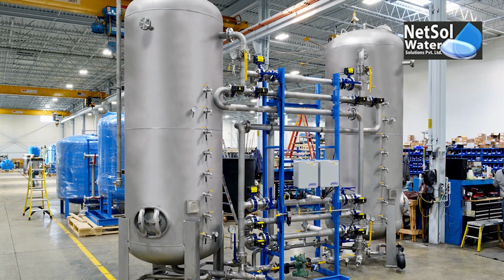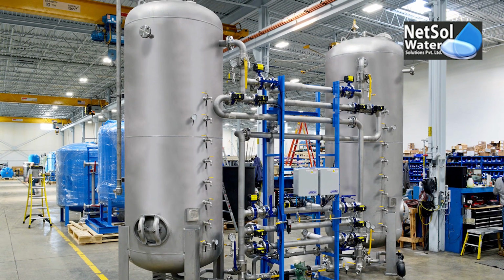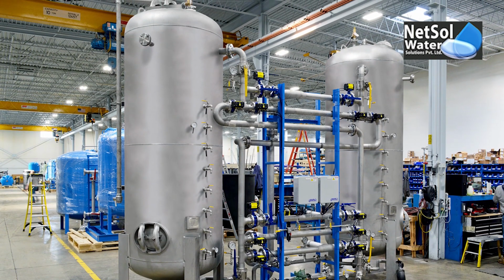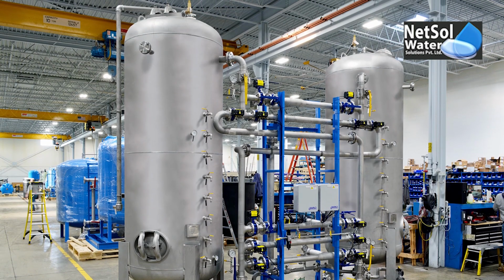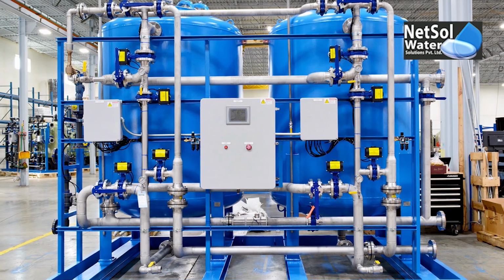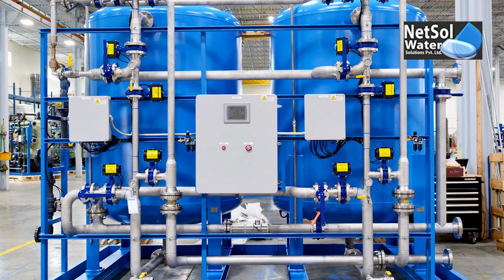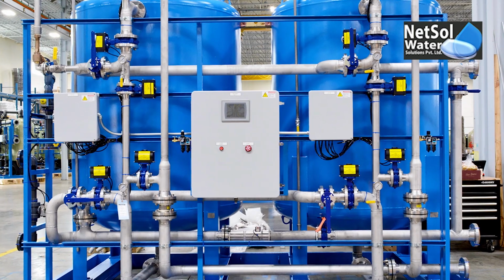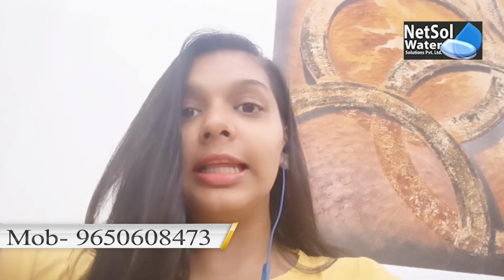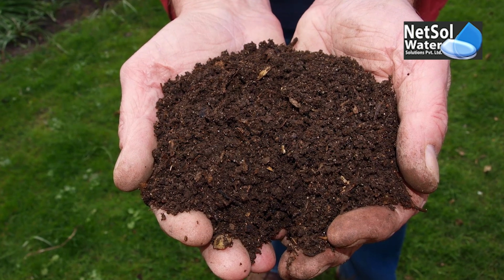One advantage of using activated carbon is its low operating cost, and virtually fail-safe operation once it is installed. Do you know that there is one disadvantage? Chlorine is removed from the topmost layer of the media, but the activated carbon provides a damp environment ideal for the growth of bacteria. Bacteria can cause problems, but by using different techniques we can eliminate it, by using carbon in a pre-treatment to the reverse osmosis. The second working of the activated carbon filter is removal of organic matter.